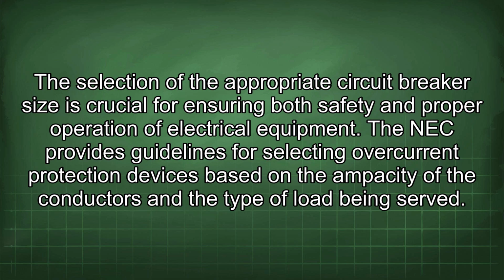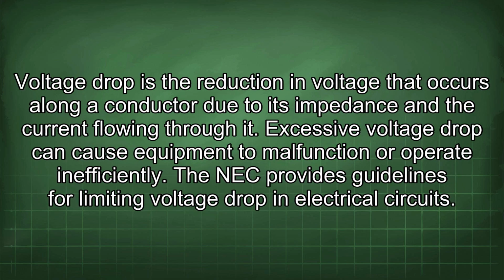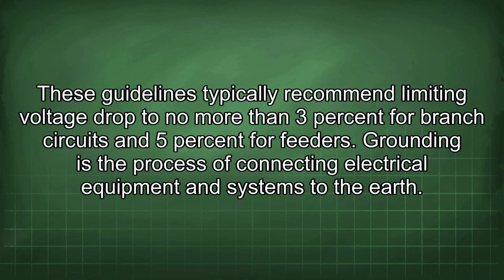load being served. Voltage drop is the reduction in voltage that occurs along a conductor due to its impedance and the current flowing through it. Excessive voltage drop can cause equipment to malfunction or operate inefficiently. The NEC provides guidelines for limiting voltage drop in electrical circuits. These guidelines typically recommend limiting voltage drop to no more than 3% for branch circuits and 5% for feeders.